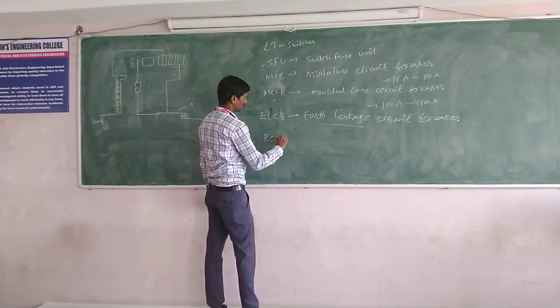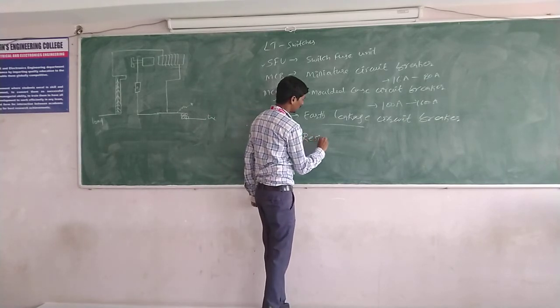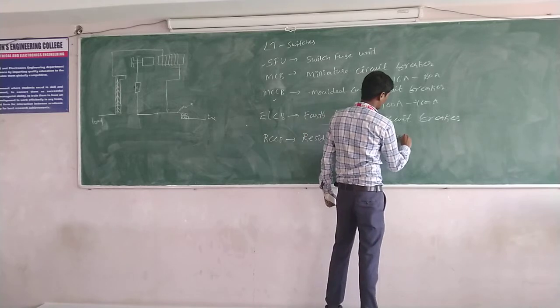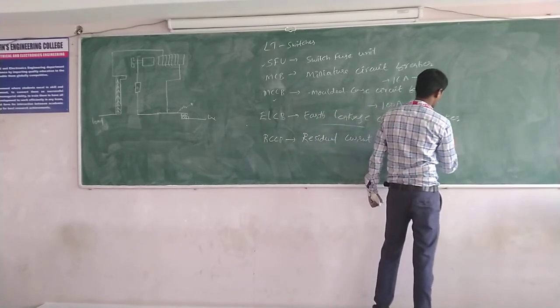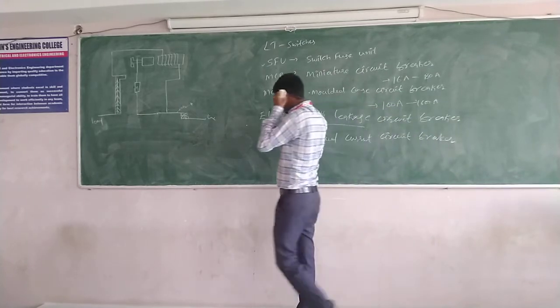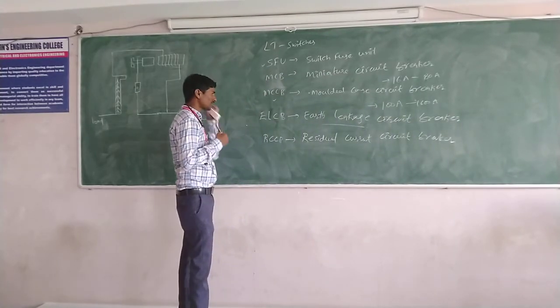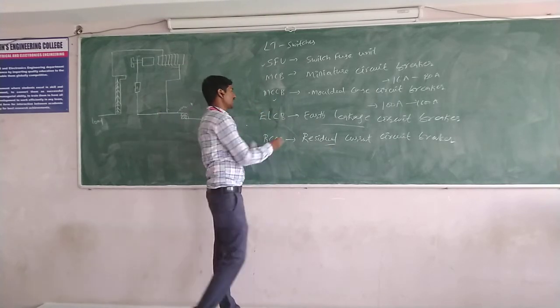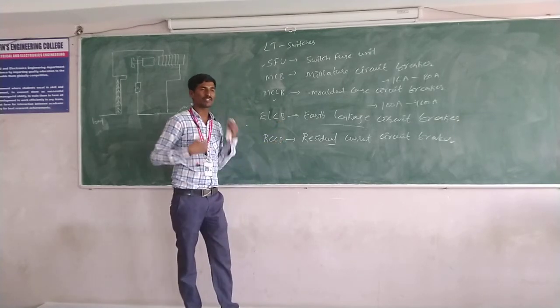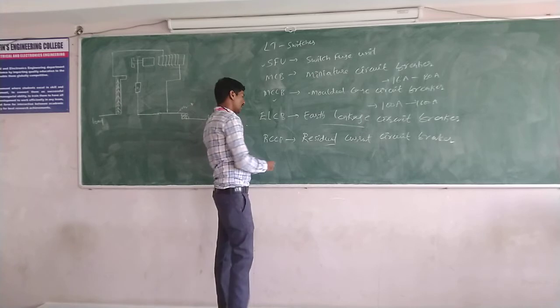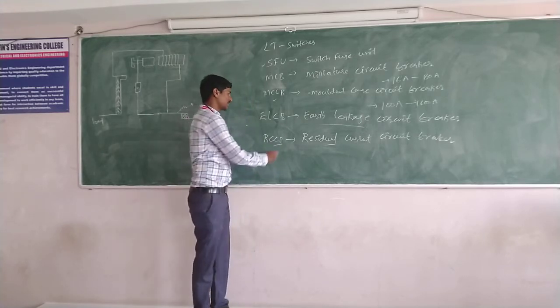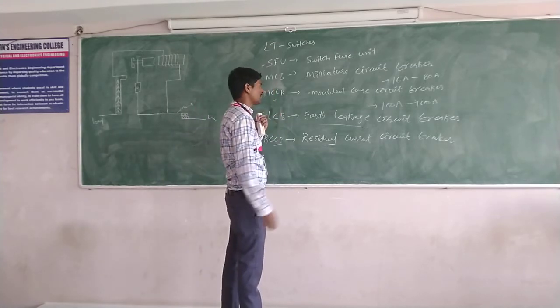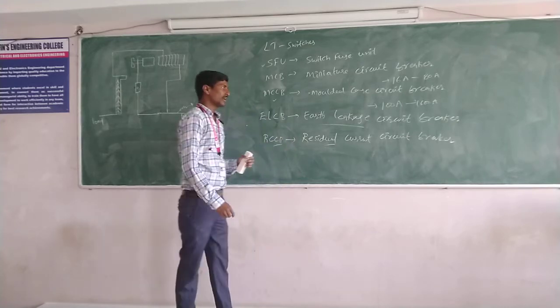Next is RCCB — Residual Current Circuit Breaker. The ELCB consists of two types: one is the voltage-operated type and another is the current-operated type. We use RCCB, which is the current-operated type. This RCCB also comes under ELCB only. RCCB is much more commonly used compared to the voltage-operated ELCB.